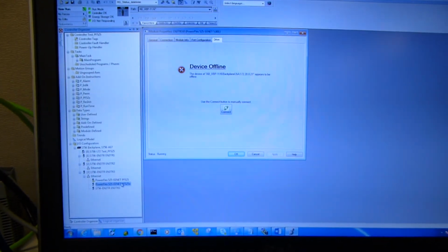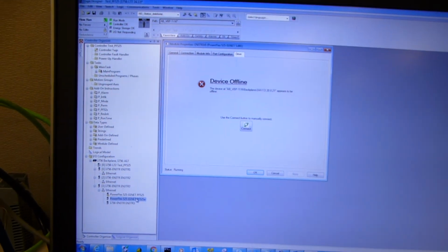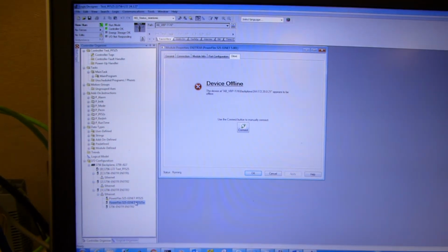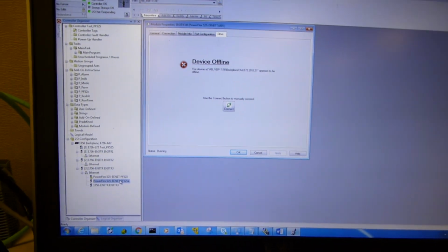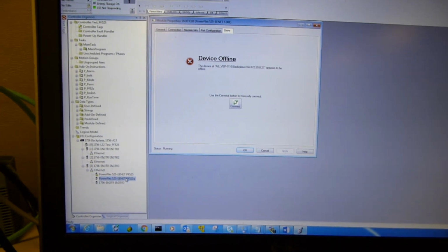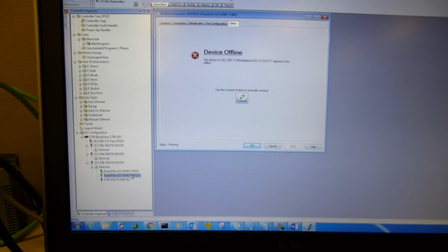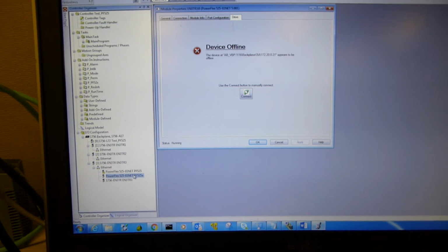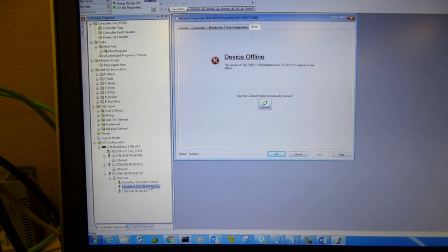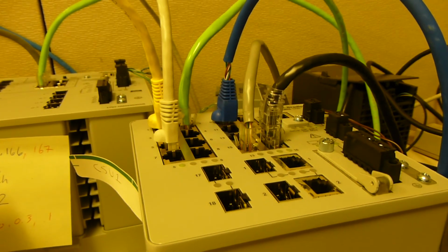So at this point, we have removed that extra programming of the IP parameters, and we've basically taken a PowerFlex drive out of the box, powered it up, wired it in, cycled power, and it's up and running without doing anything other than an electrician wiring it in. So it's a very powerful feature of using automatic device configuration with DHCP persistence on a Stratix 5700.